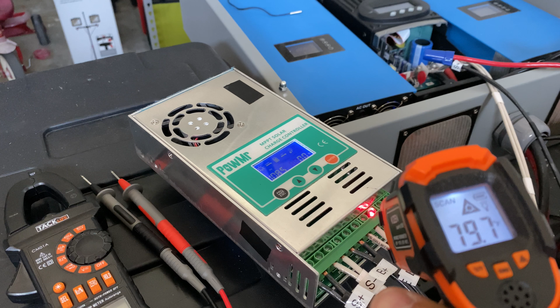It feels like this device is just overheating and reducing output. When I touch it, the hottest part is the back of the unit, but let's check the actual temperature. The terminals are pretty cold, but the back side of the unit is up to 114 Fahrenheit. To me it looks like this device is overheating and reducing production, and that's why we see this disconnection.